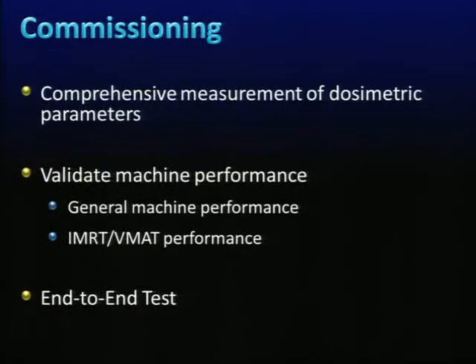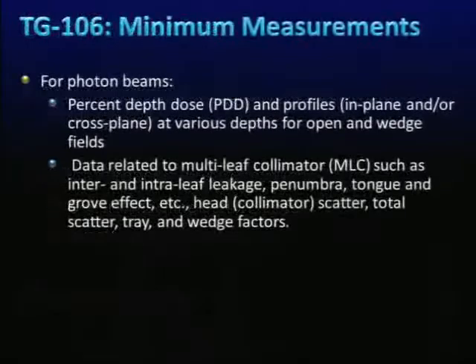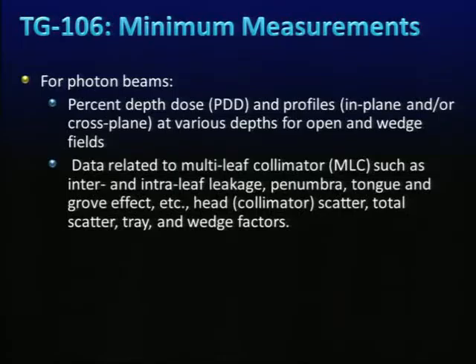Commissioning has three major parts: first, comprehensive measurement of dosimetric parameters; second, validating machine performance including general, VMAT, and RapidArc performance; and third, end-to-end testing. A good guideline is AAPM TG-106, which specifies minimum requirements for PDD and profiles at various depths and field sizes, MLC-related data such as inter- and intra-leaf leakage, penumbra, tongue-and-groove effects, head scatter, total scatter, tray, and wedge factors.